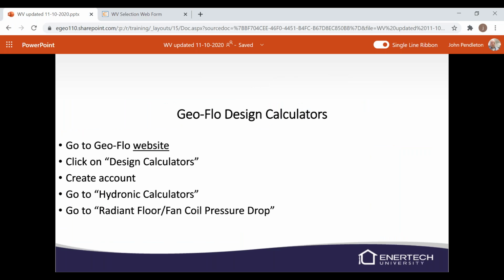We also have some Geo-Flo design calculators that work well if you need to size the pump, especially if you're going to size the external pump for your zones. Geo-Flo is real good about not sending you a bunch of junk email and stuff, so I would recommend going to Geo-Flo, to their website, and creating an account. And then you can click on the design calculators. And they have quite a few on there. They have loop sizing calculators, pump sizing, all different kinds of calculators there.